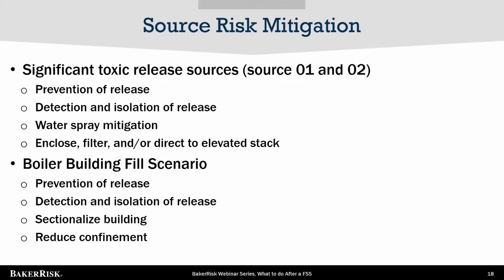For the boiler building fill case scenario, for prevention of the release, this is around the natural gas piping to the boiler. So how much of that piping is inside the building? Can it be minimized and just travel a shorter distance to go outside and travel outside rather than inside the building? Are there flanges? If there are, can we minimize flanges? For detection and isolation of the release, is there flammable detection and shutdown capability right now? If there is, can we add more, increase the detection, put more detectors out there? If it's manual shutdown or there aren't shutdown systems, can we add those?